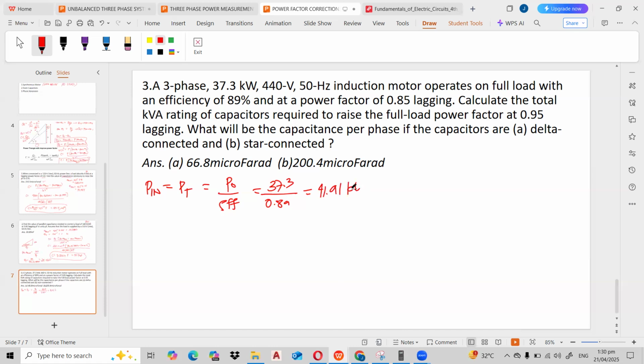Okay, so kilowatts. Dito muna tayo sa delta connected. By formula, we have C equals to PT, tangent theta old minus tangent theta new, divided by 2 pi times the frequency times the voltage square. Magkakabago tayo sa voltage, kasi sa delta, alam naman natin, phase voltage is equals to line voltage.